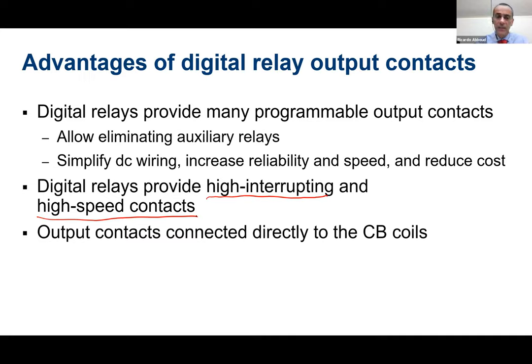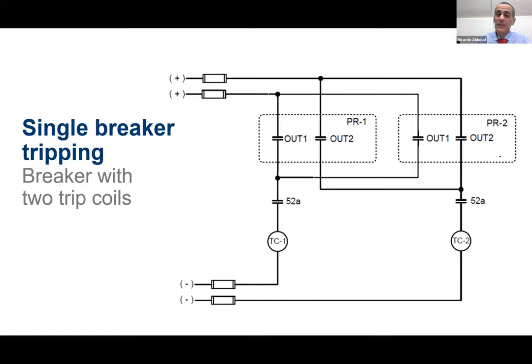So I don't need auxiliary relays for the tripping and closing. So basically I'm eliminating the auxiliary relays that are necessary for the electromechanical relays. So this will simplify the DC wiring. And also this will increase the reliability because I have fewer devices being applied, and this will increase the speed to clear the fault. And of course, it will reduce cost. So this is one example of a trip circuit for a digital relay. It can be simple like that.